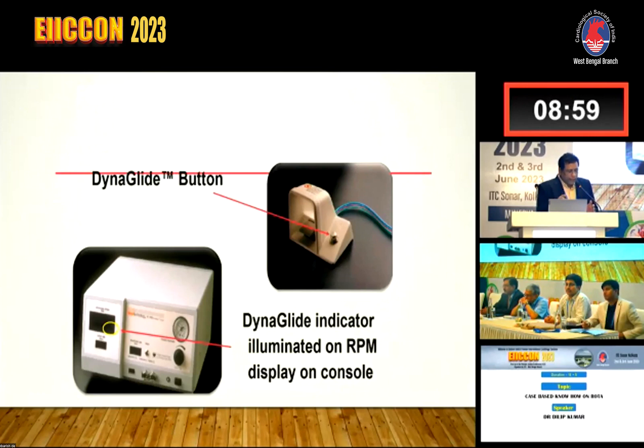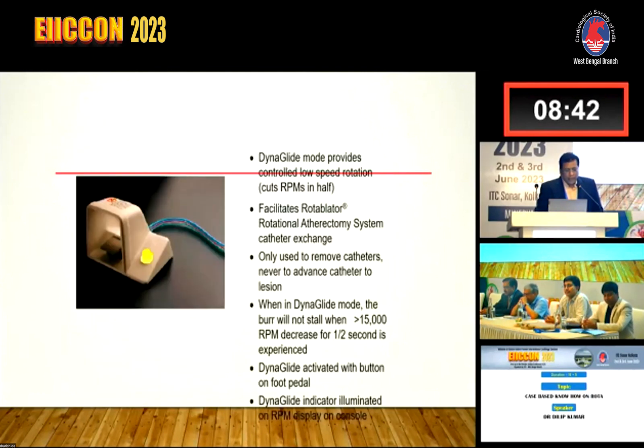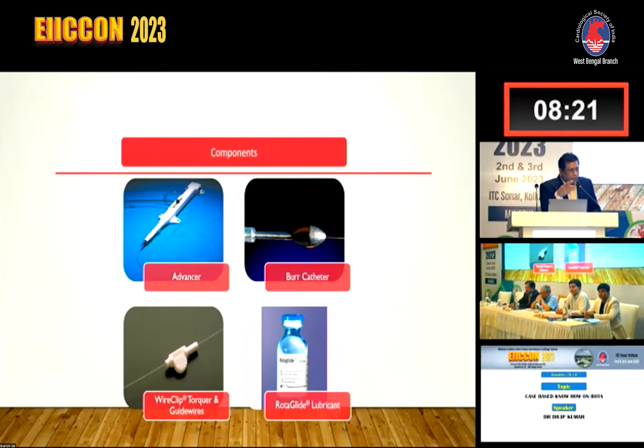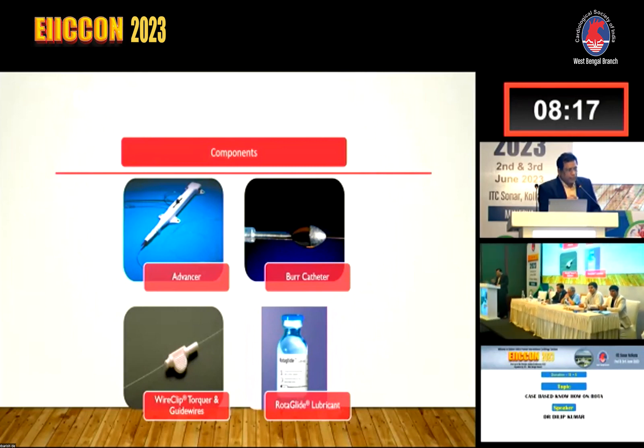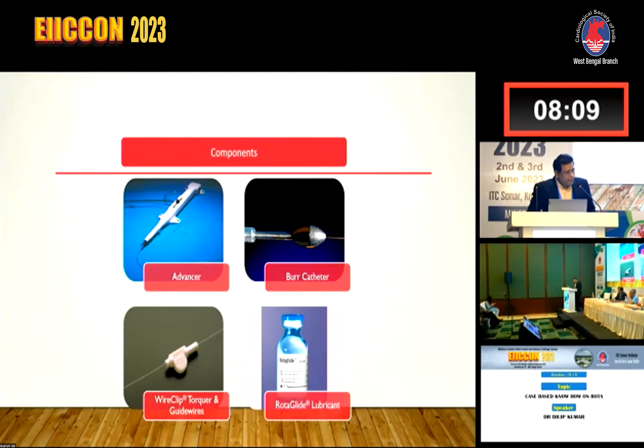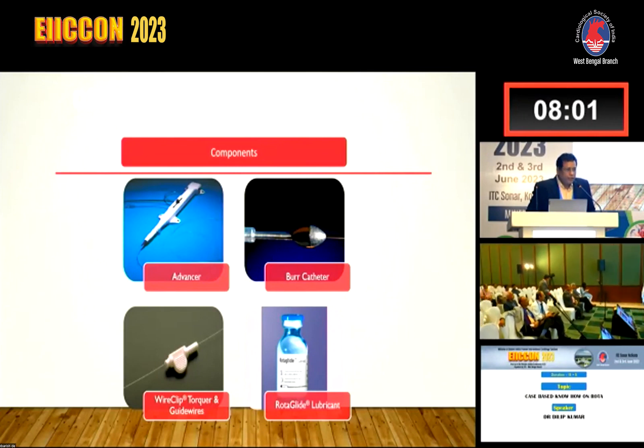DynaGlide means the rotational speed is not 150,000-170,000 - it's just half of that, about 70,000 to 90,000, so it doesn't injure the vessel. You can take out the wire after activating dynec glide mode. Some operators activate dynec glide to advance the wire when it has come inside the mid LAD, but the company discourages doing this. DynaGlide mode is always to withdraw and exchange the wire.